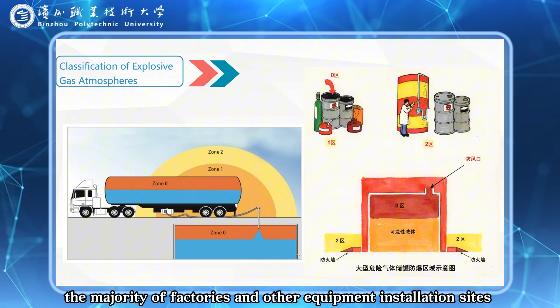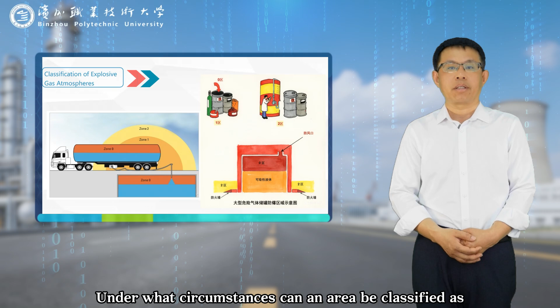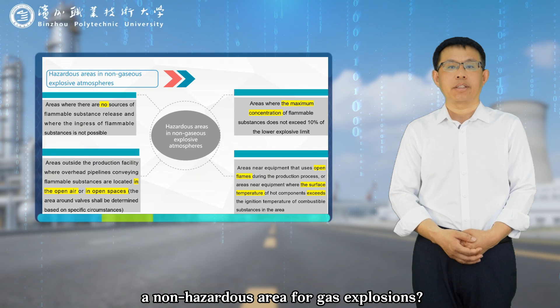That is, the majority of factories and other equipment installation sites should be classified as Zone 2 or non-hazardous areas. Under what circumstances can an area be classified as a non-hazardous area for gas explosions? First, areas with no sources of flammable substance release and where the ingress of flammable substances is impossible.